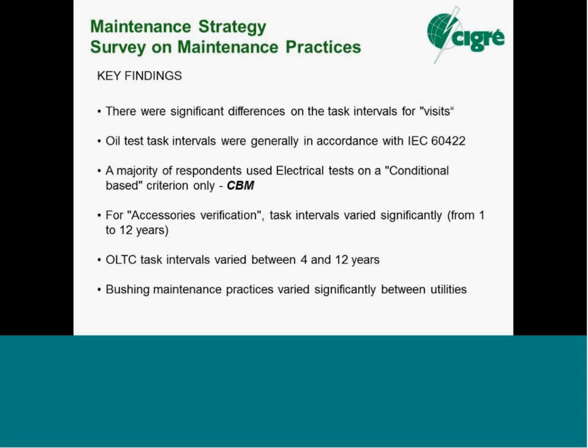When you think of the active part immersed in the oil, testing, DGA is an extremely important monitoring technique. For condenser bushings, there is the possibility of online monitoring, where one might have to tap continuously. But if you don't have that, then, taking the risk identified from the reliability survey, there should be some effort in doing some electrical testing, especially at least at the midlife age of these bushings.